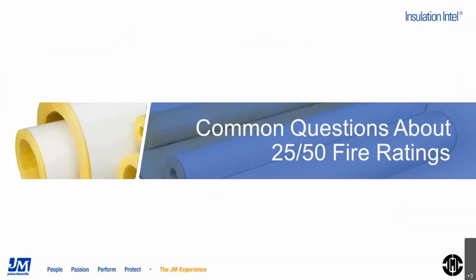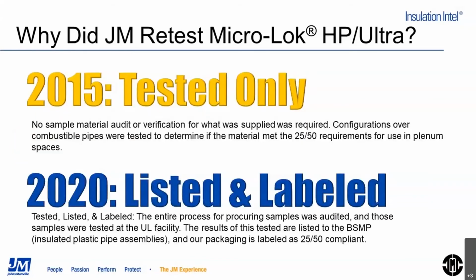And now I'll be wrapping up with some of the common questions that we usually hear about the 25/50 fire rating. The first one: why did we retest Micro-Lok HP and Micro-Lok HP Ultra? Some of you may be familiar that we've actually done third-party testing back in 2015, and we did get the 25/50 rating, so that was all good. But in 2020, we went through the whole process of listing and labeling, because in 2015 there was just the testing, and now we had UL audit the entire process, from procuring to producing sample boards, and then all of this was tested at the UL facility.